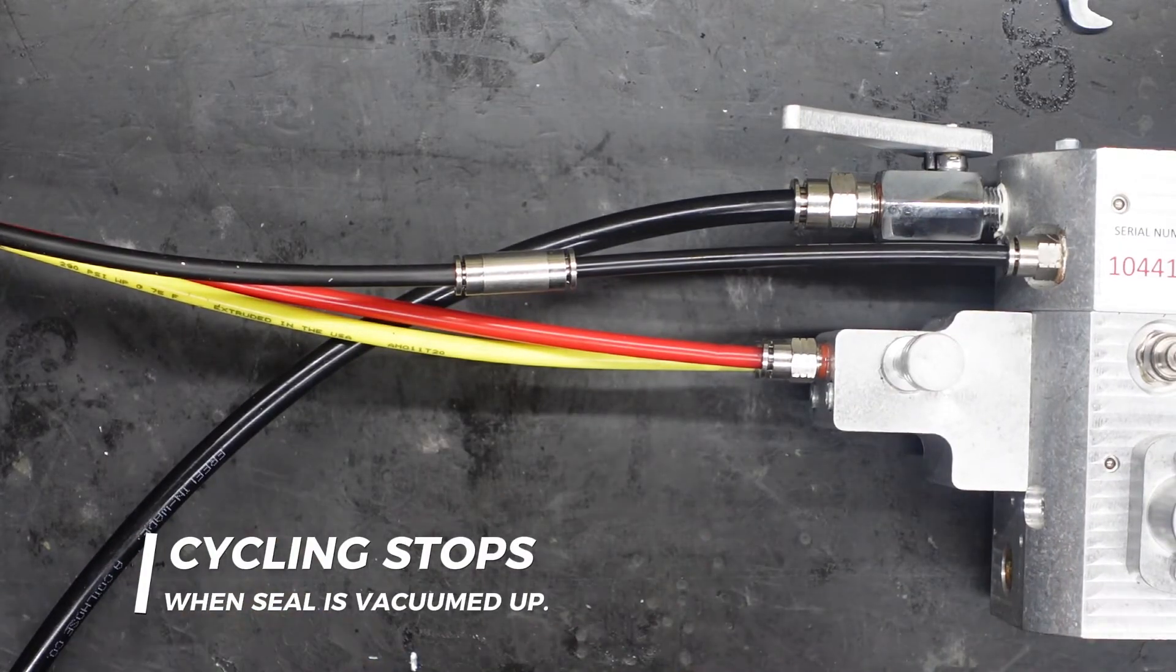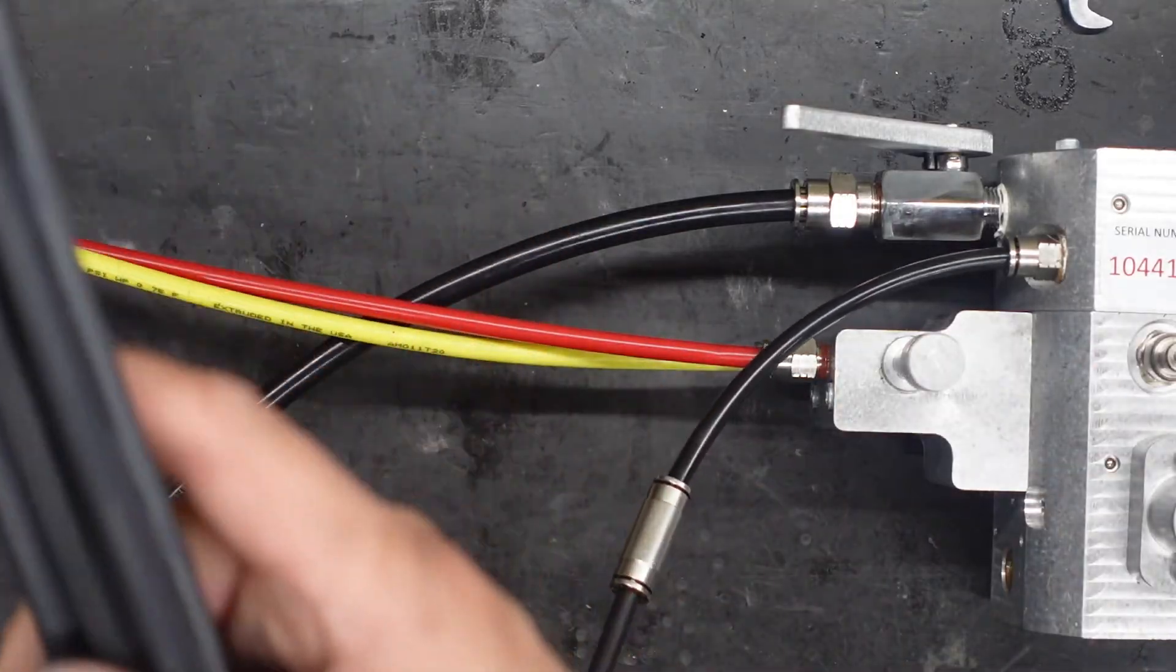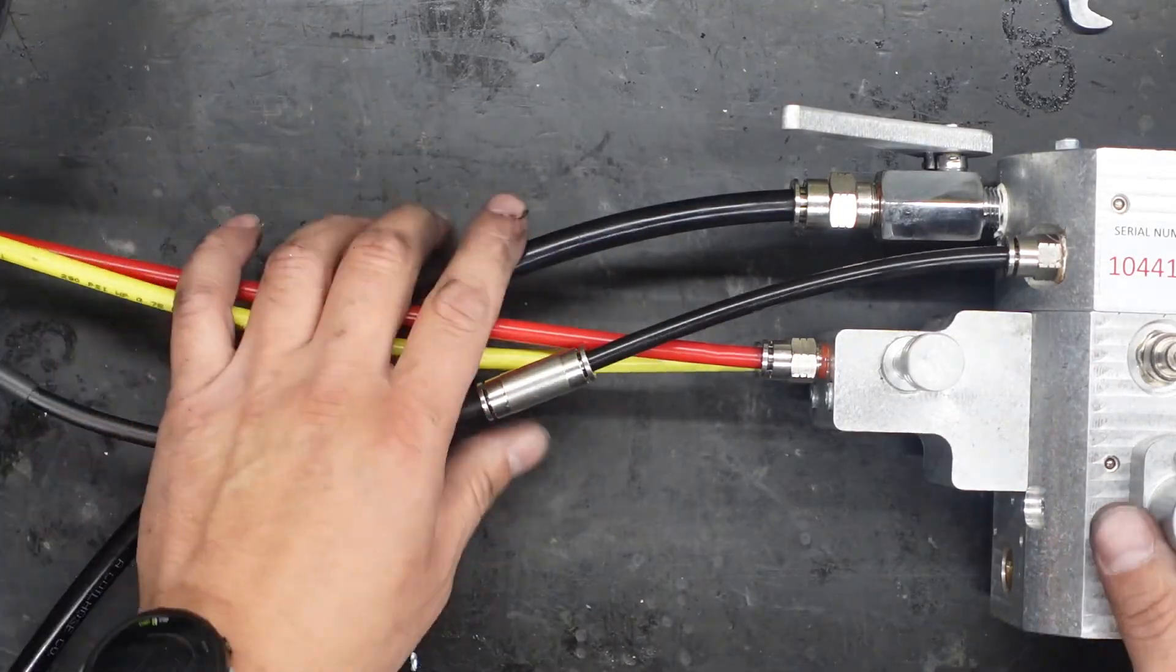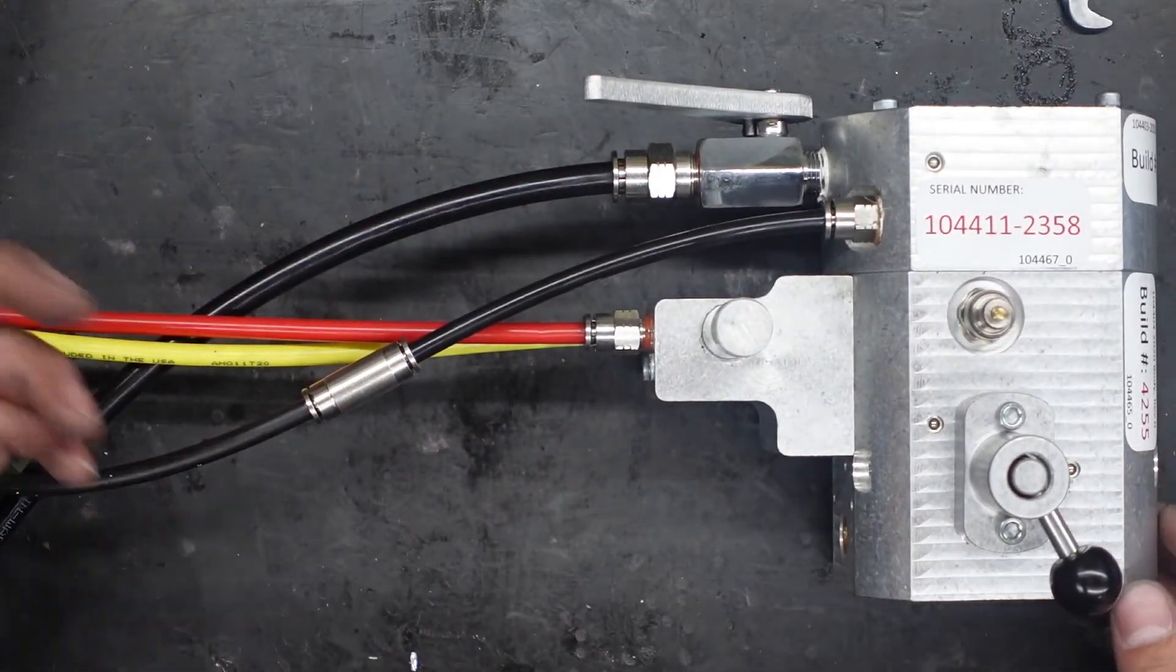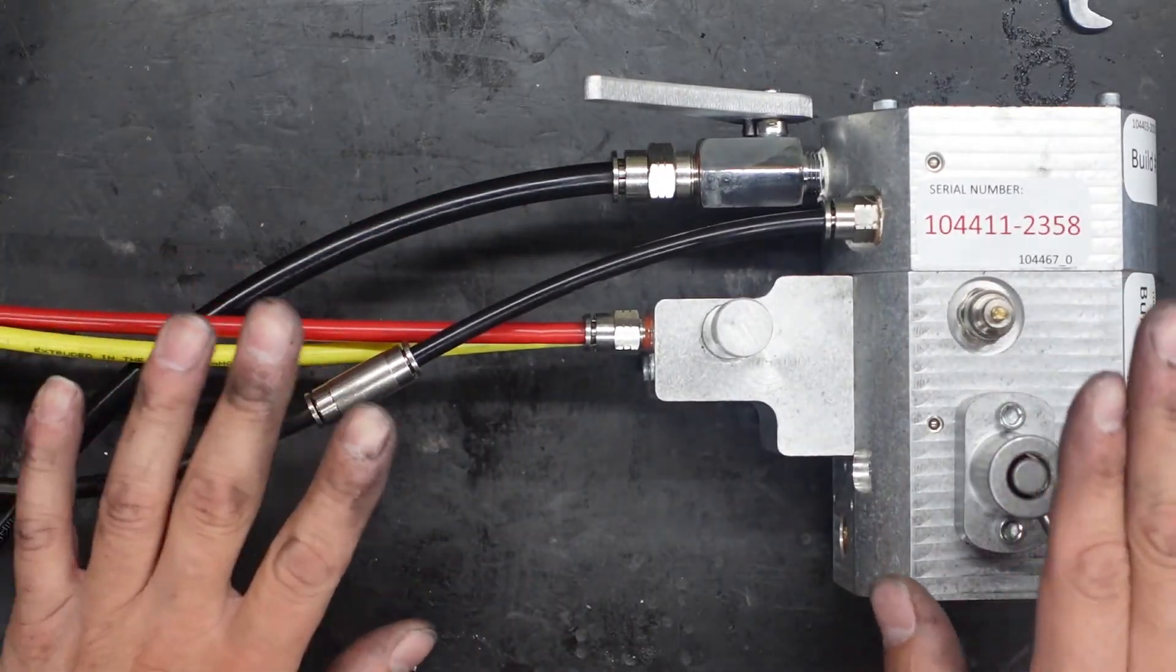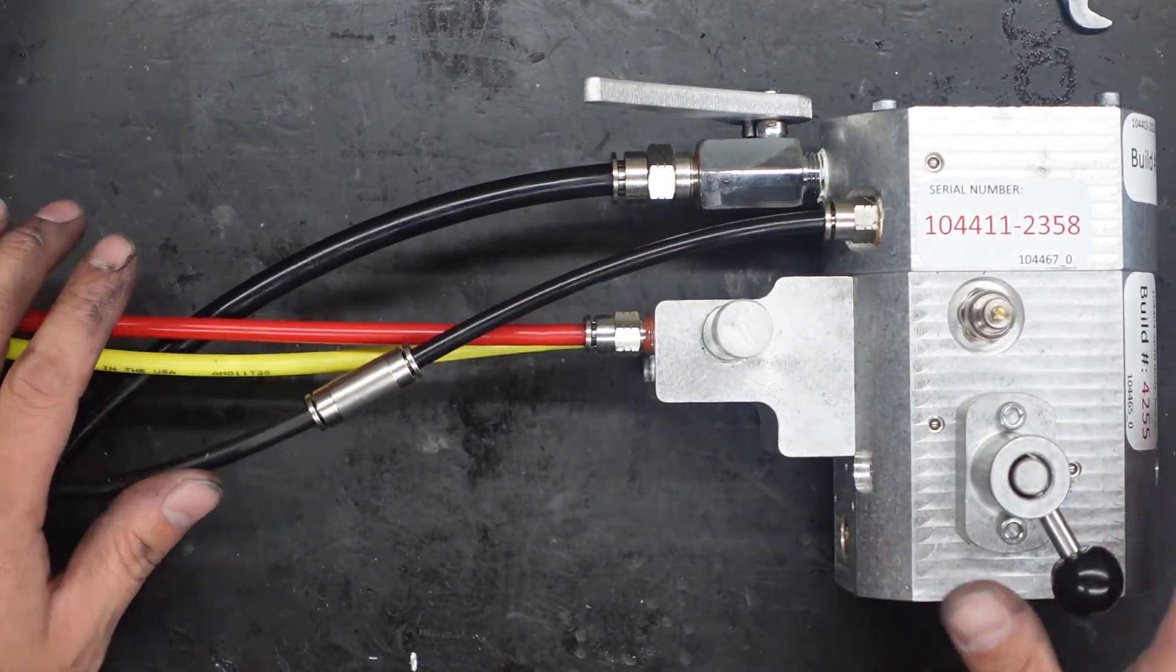That's about how long it should take to vacuum out all the air out of that seal. A little longer because it's got 50 feet of airline as I only have a foot here. But if it continues cycling after that we have another issue we need to look at. If it stops then it is working properly.